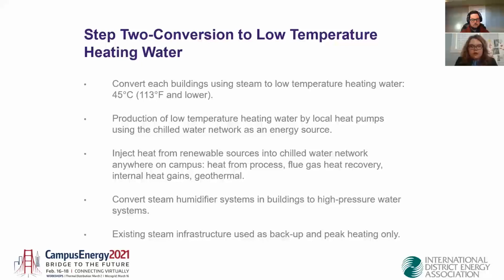So we have a heat recovery on the flue gas from one boiler. So that's a great source of heat. So when we cool those exhaust gas, that heat is sent into that chilled water network and it can be recovered anywhere on campus. So we're recovering, again, heat from processes, either if it's a laboratory or a server room or something like that, and internal heat gains as well, like for a gym or an ice rink. So all that heat is recovered and sent to that chilled water network. And of course, geothermal is going to come into play in the future as well. And when we can, we convert steam humidifier to high pressure water systems to remove load on the steam network. And the steam is kept for backup for heating of the building.